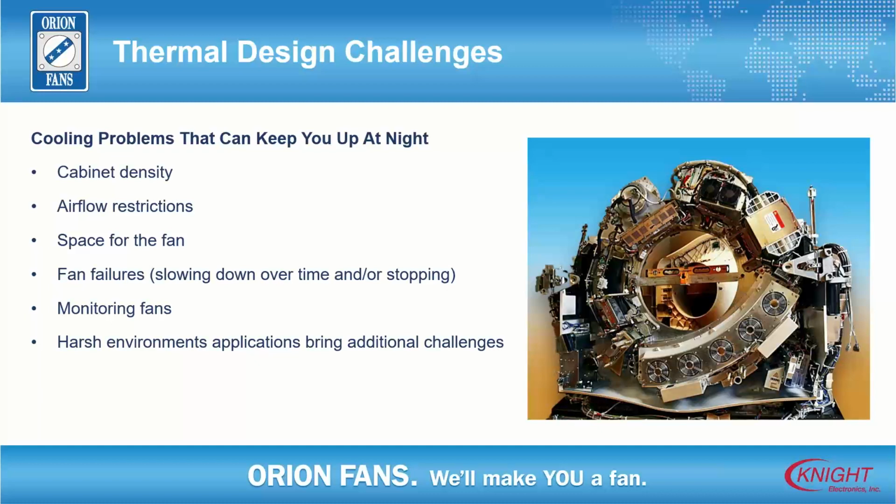So hot air is hard on the fan too, as all other harsh environments are hard on the fan. Fan failures tend, over time, to slow down or stop, which in harsh applications can be a real problem. Most fan failures are just a stop. They don't tend to slow down and get slower and slower. Usually, if that happens, it happens very quickly. The failure mode on fans most of the time is the bearings. That is the weakest point in the system, and that's basically what sets the L10 life we use for them.